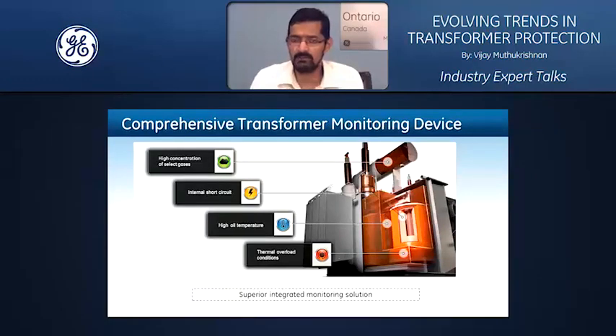Now, just going into how it really works. Think about a transformer: you are going to bring electrical CTs and VTs into the transformer protection relay. You're going to bring in all the possible temperature monitoring into your relay. You're going to bring in any other analog parameter measurements through your DC milliampere inputs. You also have the ability to connect to a dissolved gas analyzer through communication means into the protection relay. You can also bring your entire cooling system inputs into the 845 protection relay.